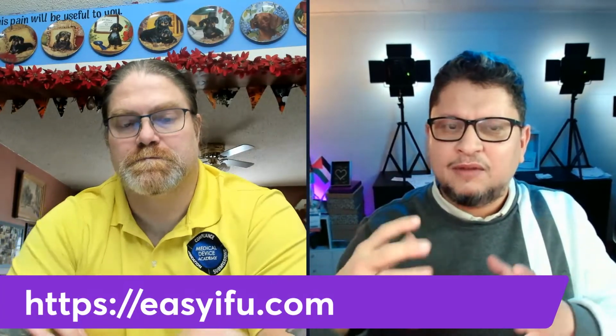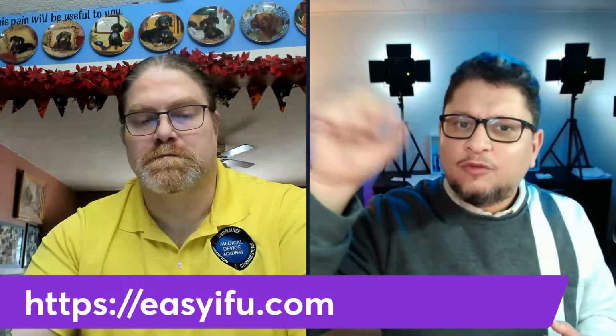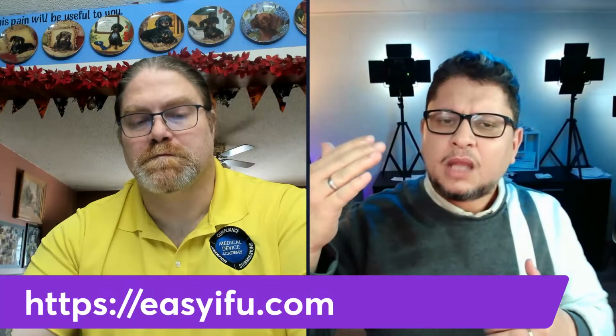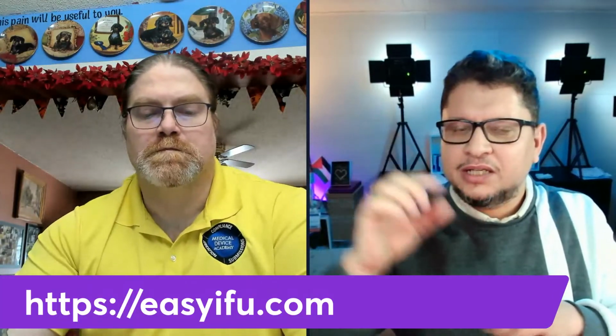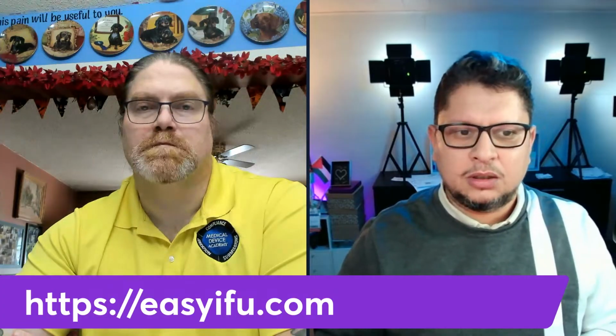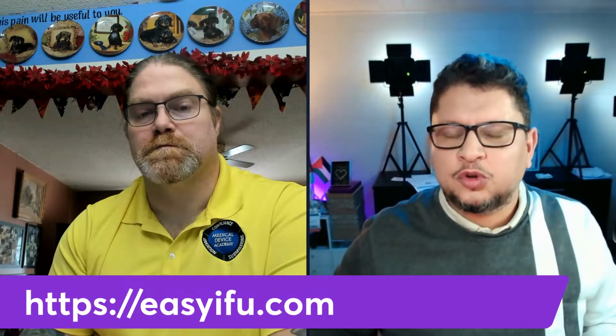Because what is also important with eIFU, when you are doing this check, is that you are on the safe side. You'll have a checklist there with all the things that say yes, it's done, it's approved, etc. And at the same time, you will receive an audit trail or audit report that will show this IFU was done at that time with this checklist, with this approver, this reviewer, with all the timeline. So this is also a document that you can show to a notified body or to an authority or even FDA, to say, here is the audit trail of the creation of my document. Here is version 1 when it was created, version 2, here are the changes. So you can in one page have all the history of it, which will be helpful also during an audit. Instead of you trying to explain how things were moving, we just create this report, and then you can click on a button and show it directly to the authorities.